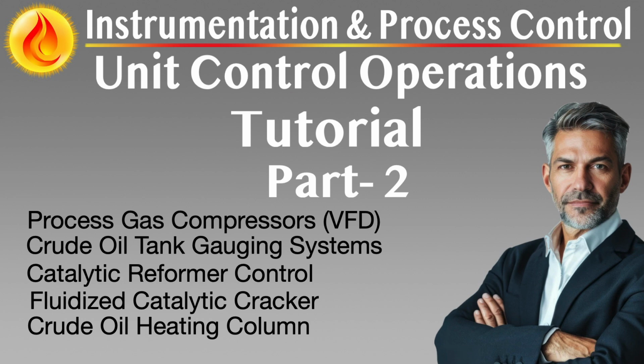Today's high-performance gauging systems deploy non-contact radar-level sensors, servo gauges, and guided wave radar (GWR) probes that provide continuous high-accuracy measurements of crude oil level, interface, oil-water, and free water bottom (FWB). These sensors are typically certified for custody transfer applications per international standards, e.g. API 3.1b, OIML R85, ensuring traceable and legally defensible measurements.